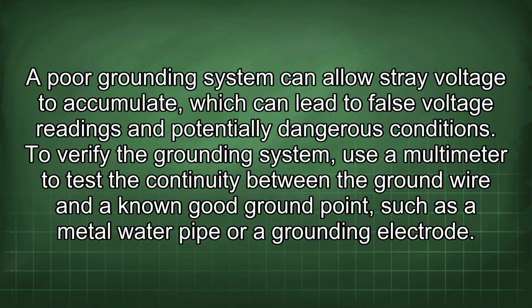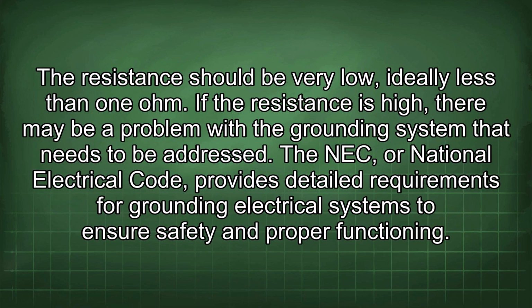To verify the grounding system, use a multimeter to test the continuity between the ground wire and a known good ground point, such as a metal water pipe or a grounding electrode. The resistance should be very low, ideally less than 1 ohm. If the resistance is high, there may be a problem with the grounding system that needs to be addressed.